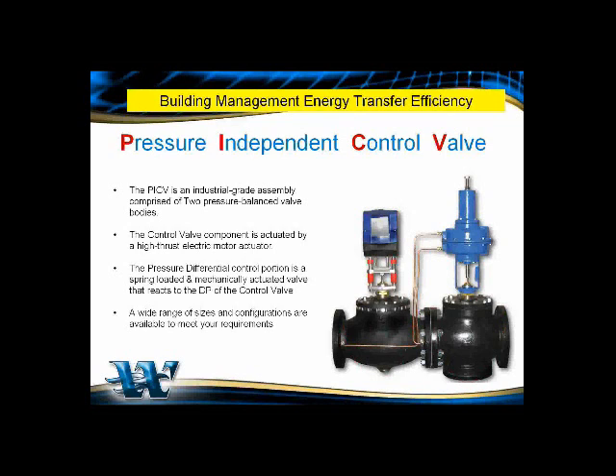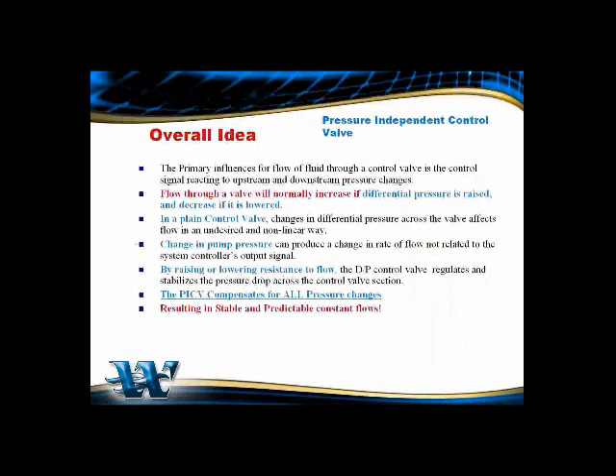I'm not going to go into a lot of details on this. If you're interested in this product, this does need quite a bit of engineering from the Warren Controls engineering people. They can help you size this, and it does need to be sized very accurately. But the concept is the primary influence is to a flow of fluid through a control valve that is reacting to a control signal. It will move based off the upstream and downstream pressure changes. So if you just use a normal control valve, the flow will increase if the differential pressure is raised and will decrease if the differential pressure is lower.